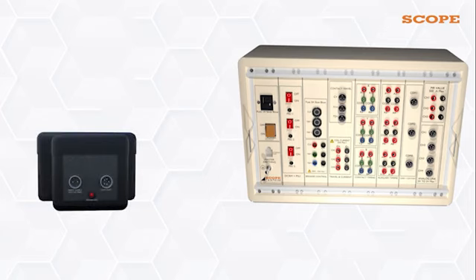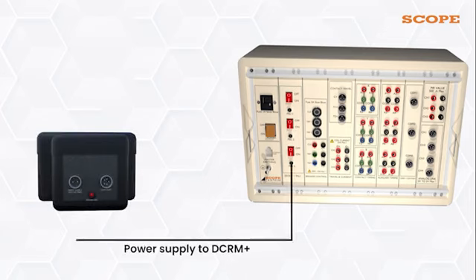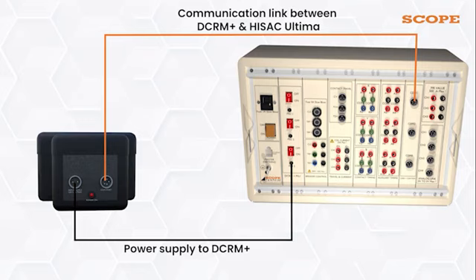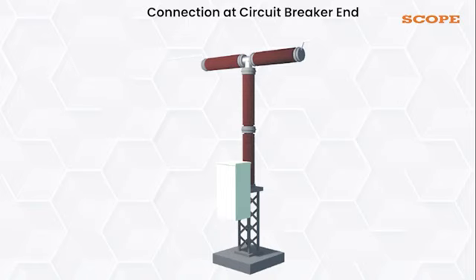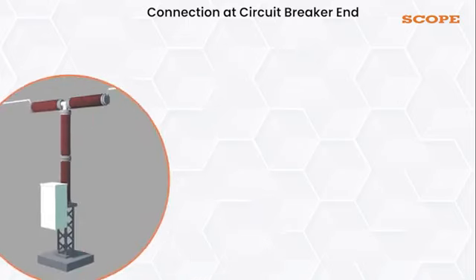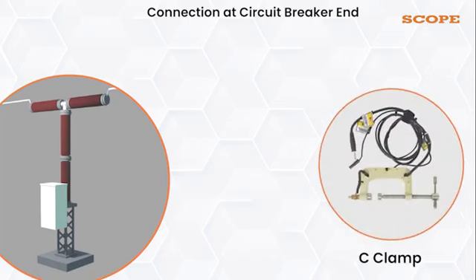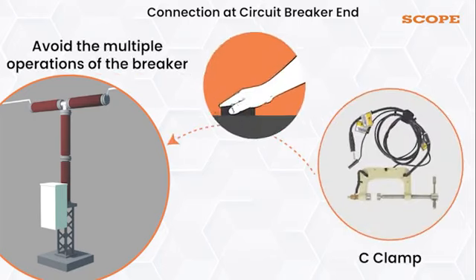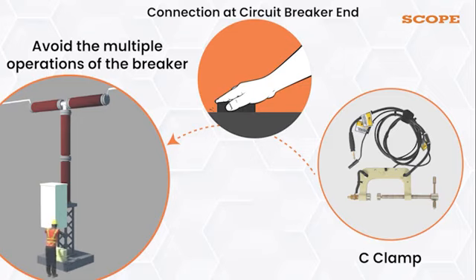We would now look for the connection of DCRM+. So to power up the DCRM+, we will use the Module 2 on Ultima. It is the bottom side of the DCRM+ where we make connections. The second connection is for the communication link by using Module 7. Let us see how to connect those. Once communication and power supply is set up, we can go for a connection at circuit breaker end. This connection is very important. We always suggest the place where C-clamp would be mounted should be cleaned properly with sandpaper so as to avoid the multiple operations of the breaker.